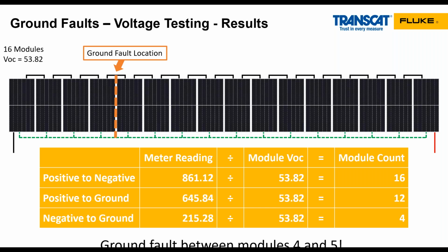Now what I need to do is go out into my array, try to figure out where modules 4 and 5 are, and then do an inspection and see what's causing the ground fault and repair that ground fault.